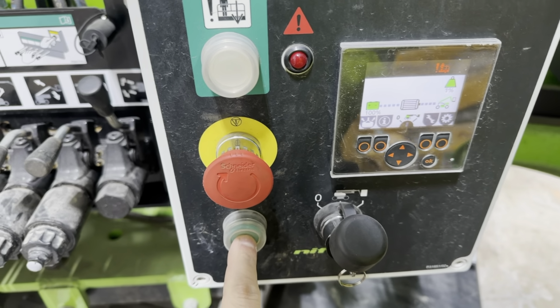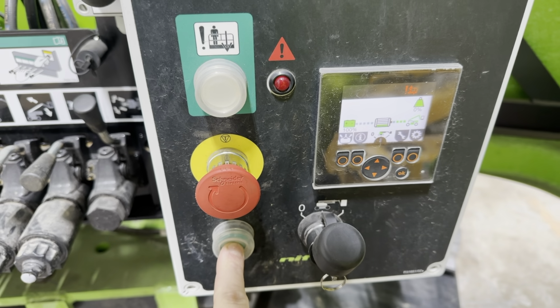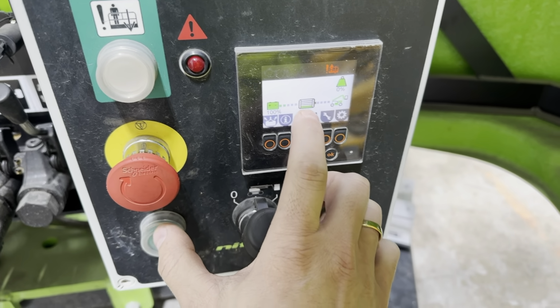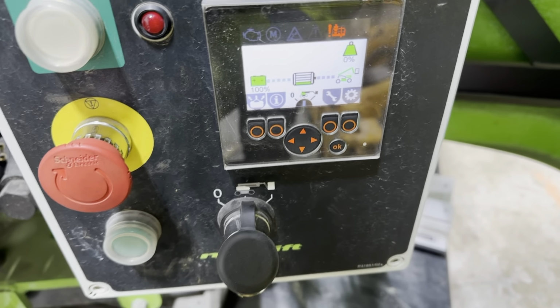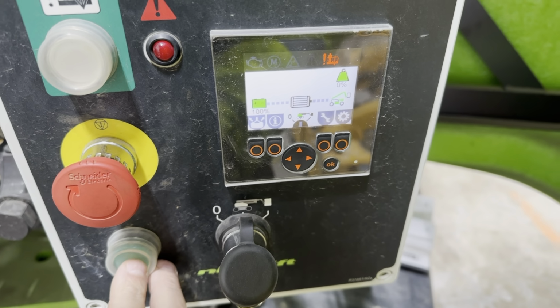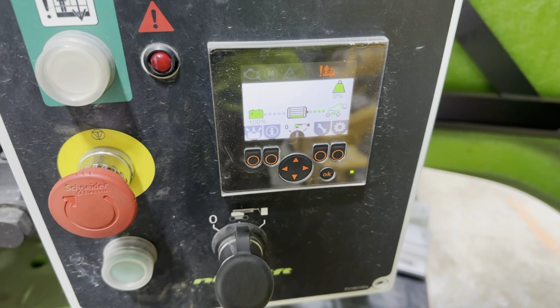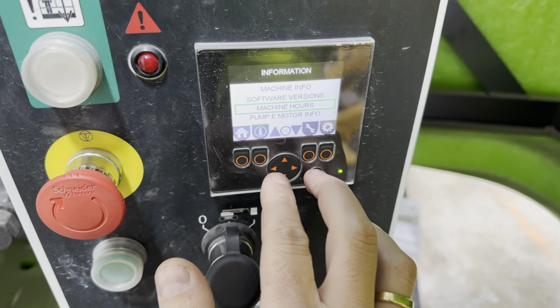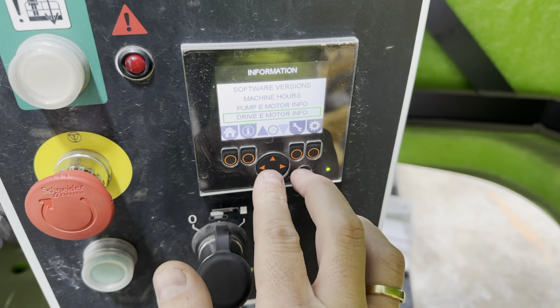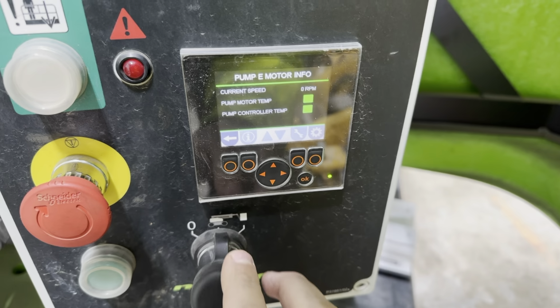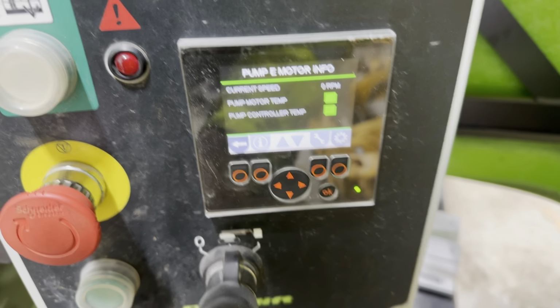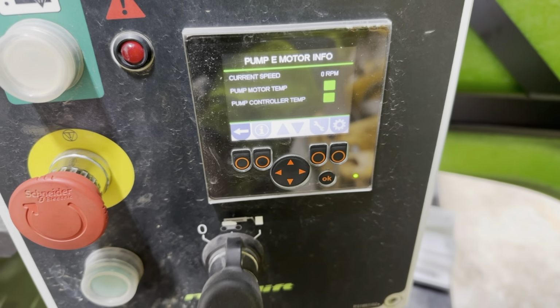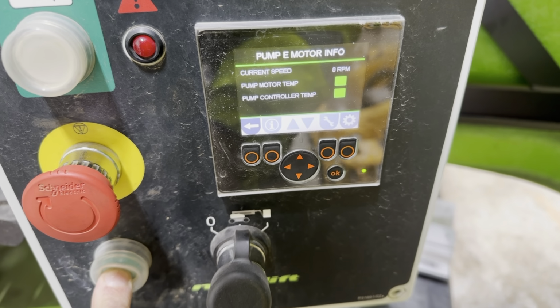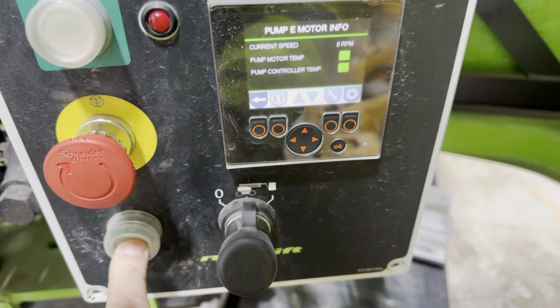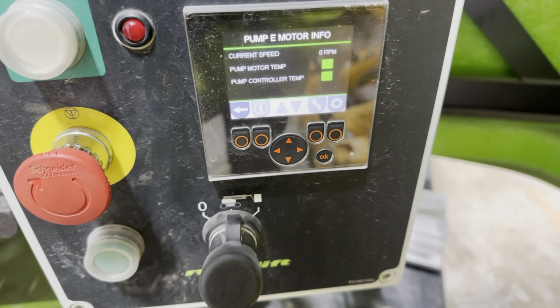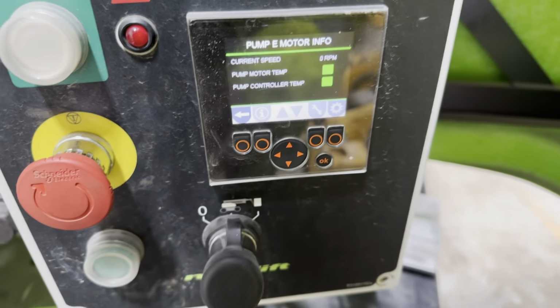So we have a motion alarm, and interestingly there were symbols showing that the motor is taking current. That's strange. That's a pump motor controller, and we got the speed and temperature readings. I'm pressing the enable button, and there's 0 RPM, so that means the motor is not running.